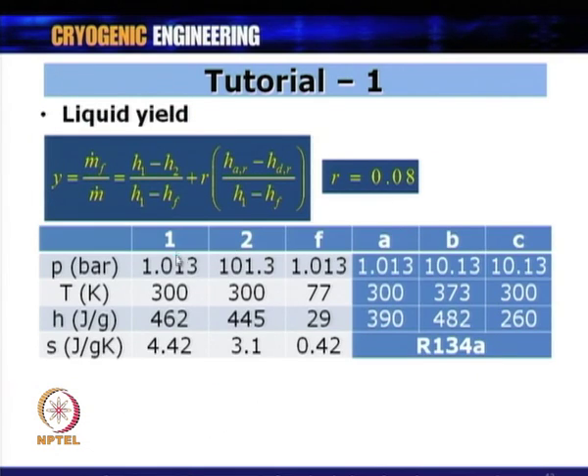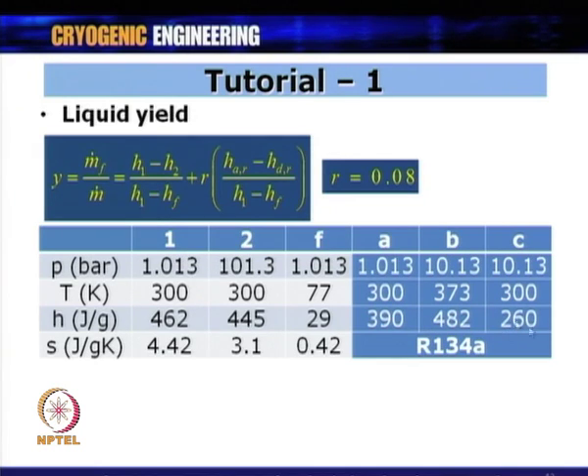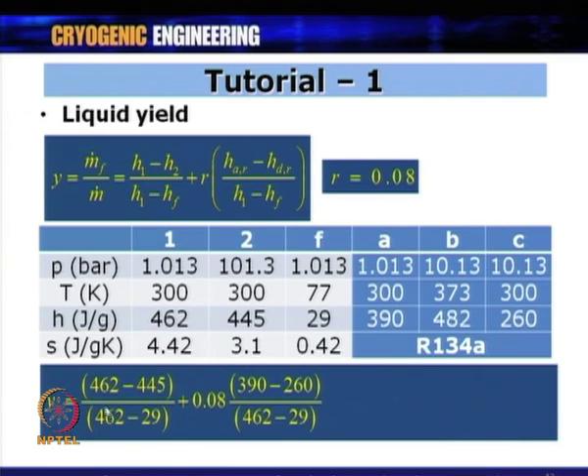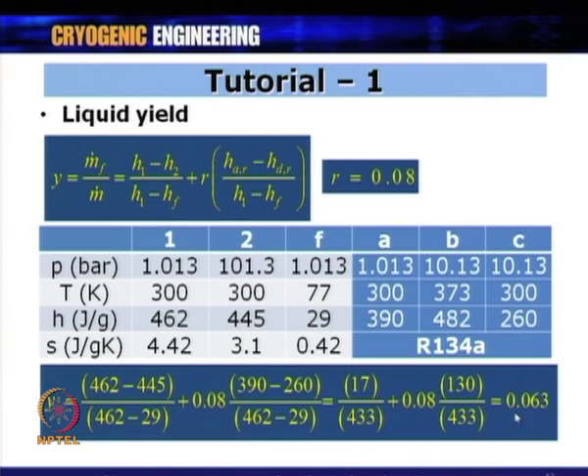The liquid yield for the pre-cooled Linde-Hampson cycle: y = (H1 − H2)/(H1 − HF) + r·(H_A − H_D)/(H1 − HF). With r = 0.08, H_A = 390, H_D = H_C = 260 J/g, H1 = 462, HF = 29 J/g: y = 0.04 + 0.08·(390 − 260)/(462 − 29) = 0.04 + 0.023 = 0.063.